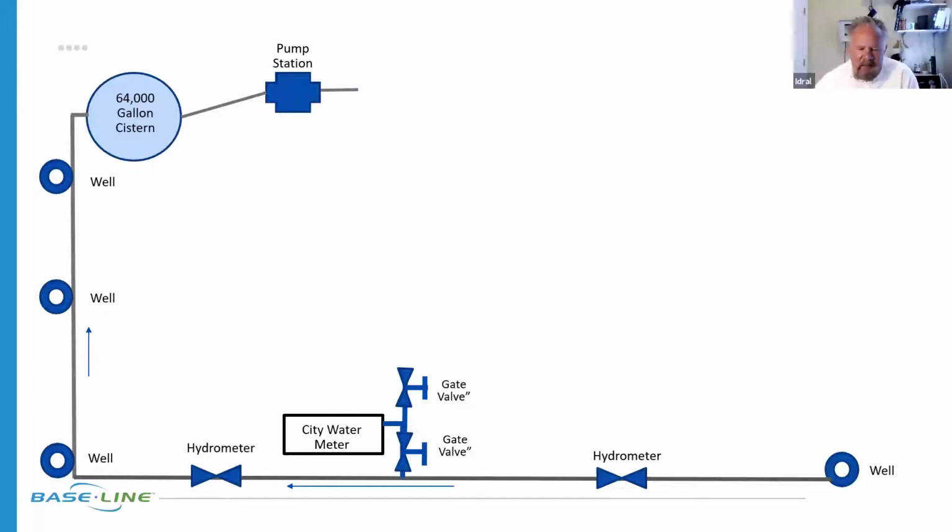Yeah, the total is about 80 or 85 gallons. So one's 10 gallons, one's 25. Not real high production as far as recharging. Okay, so wells that flow really low. They've got a city water for some makeup, and that's pretty high. If I remember, that was in the 300 or 400 GPM. Correct. We can get 350, 400 gallons a minute out of the city water fill.